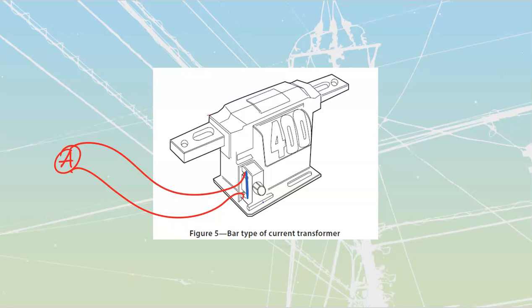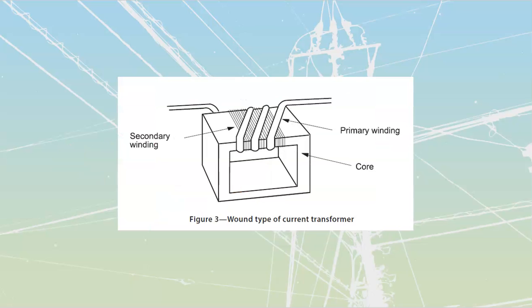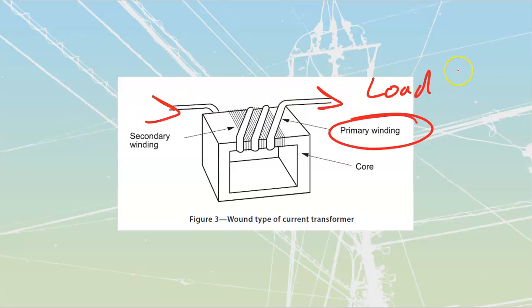Let's talk about the different types. We have wound types of CTs, which have a primary winding - that's the main load current. You'll sometimes hear it called the load winding instead of just the primary, because that's what's driving out to our load. We take the power in, drive it out to our load, and then have the secondary winding, sometimes called the metering winding.